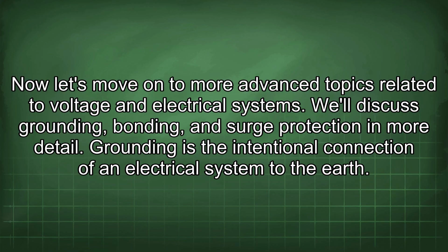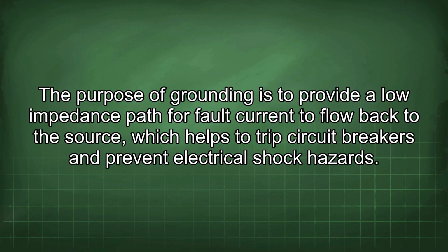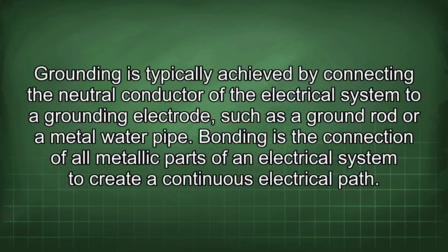Grounding is the intentional connection of an electrical system to the earth. The purpose of grounding is to provide a low impedance path for fault current to flow back to the source, which helps to trip circuit breakers and prevent electrical shock hazards. Grounding is typically achieved by connecting the neutral conductor of the electrical system to a grounding electrode, such as a ground rod or a metal water pipe.